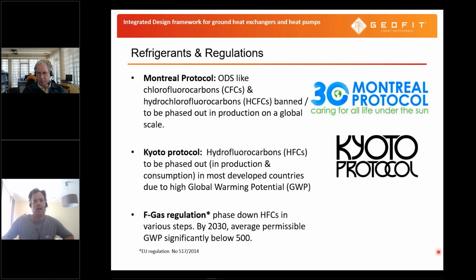So when we consider heat pump systems in general, and this is independent from the technology more or less, we have some important regulations regarding our working fluid, and this is also one crucial issue we had to deal with in the project. So you might have heard about the Montreal Protocol and also the Kyoto Protocol, which ban those CFCs, HCFCs, and so on. So what is that? This is the abbreviation for common refrigerants which have been used in the past, but due to their relatively high global warming potential, they should be banned from use in the future.